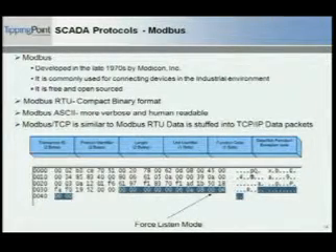Even though you have 2 bytes for length, the maximum allowed length for a Modbus protocol is only 254. So if you see any length byte greater than 254 bytes, there itself you can notice that there's an attack or somebody's trying to fudge around with your data. And I'll show you how many queries there are. Almost all the queries have a length of only 06. So that's an easy way, if you're writing an IDS kind of filter or something, you can just mention that the length has to be just 06, not more than 06.